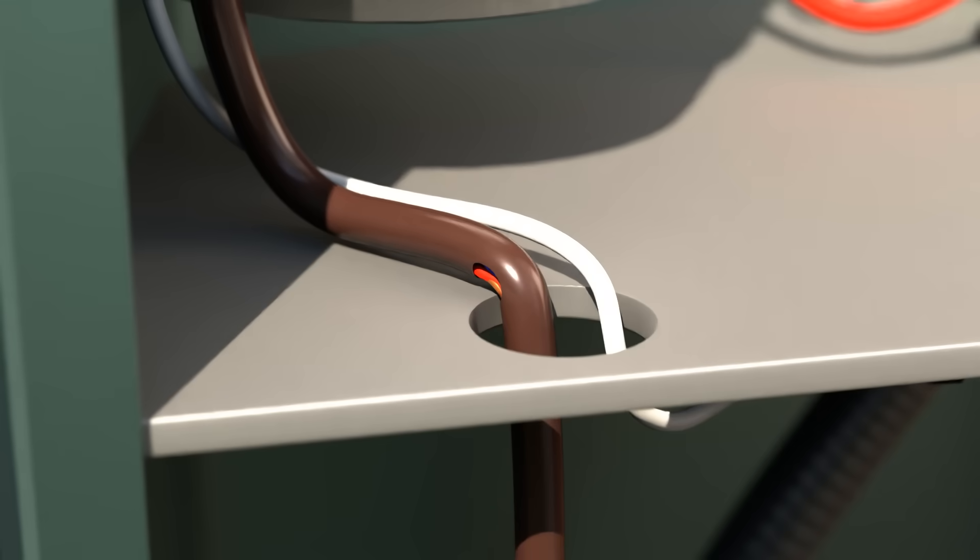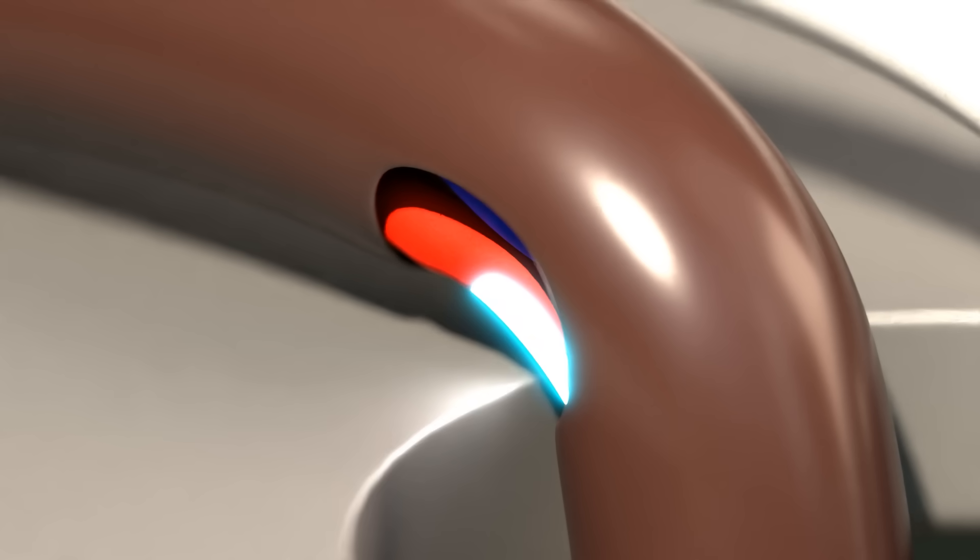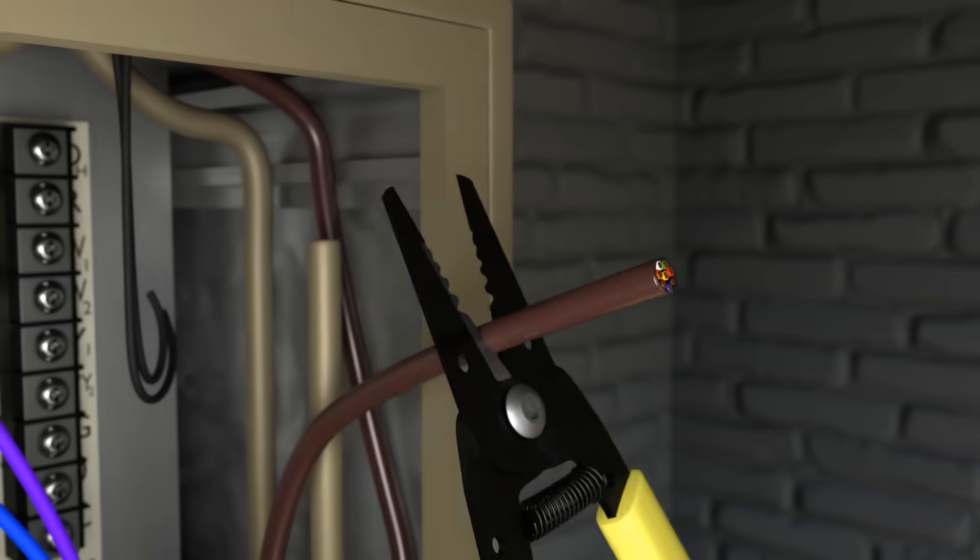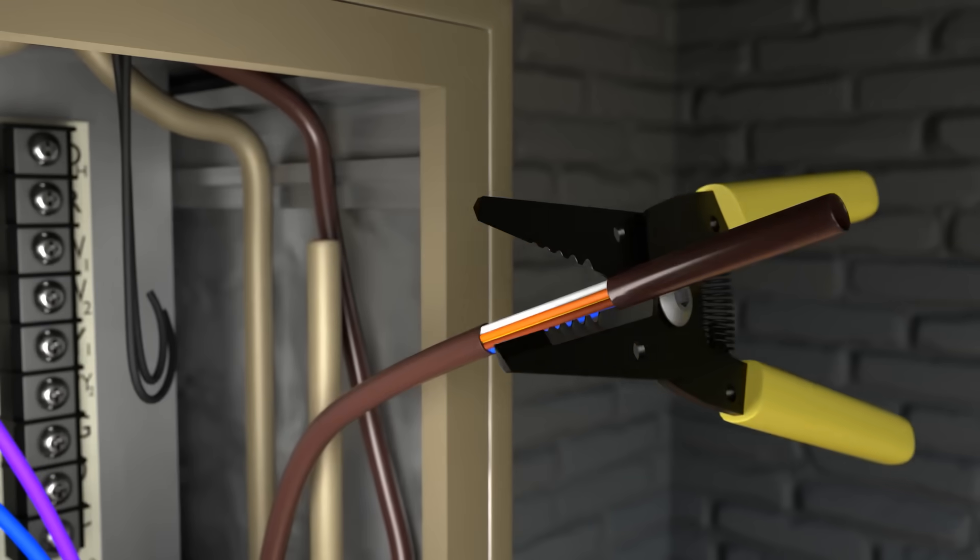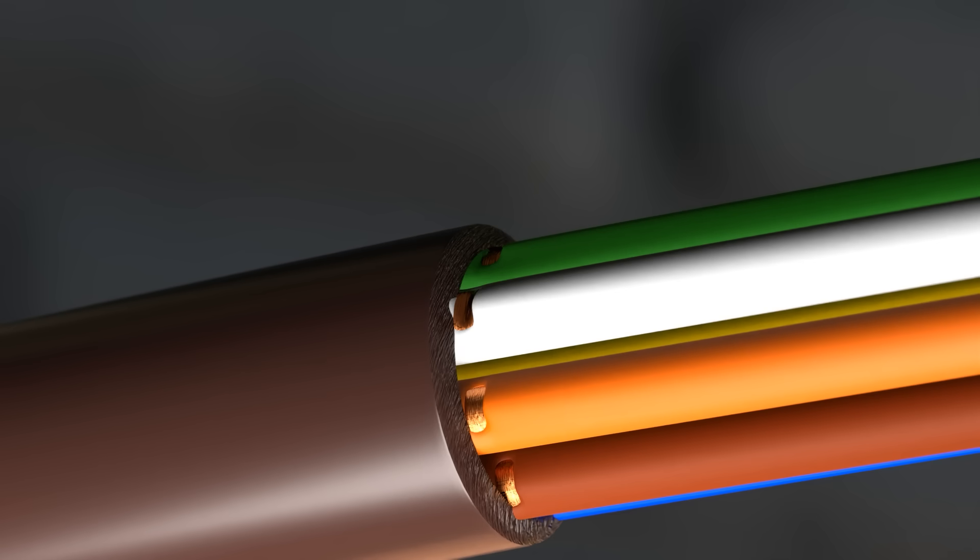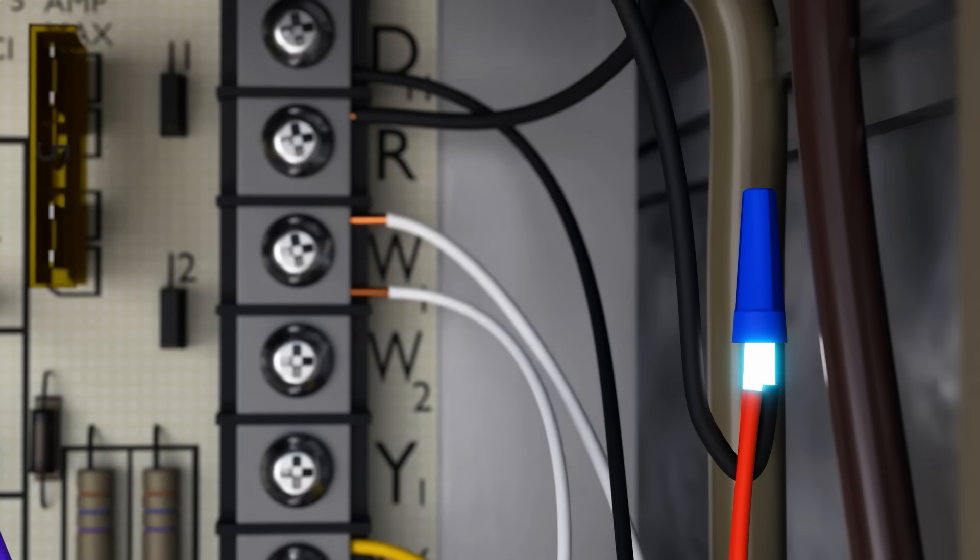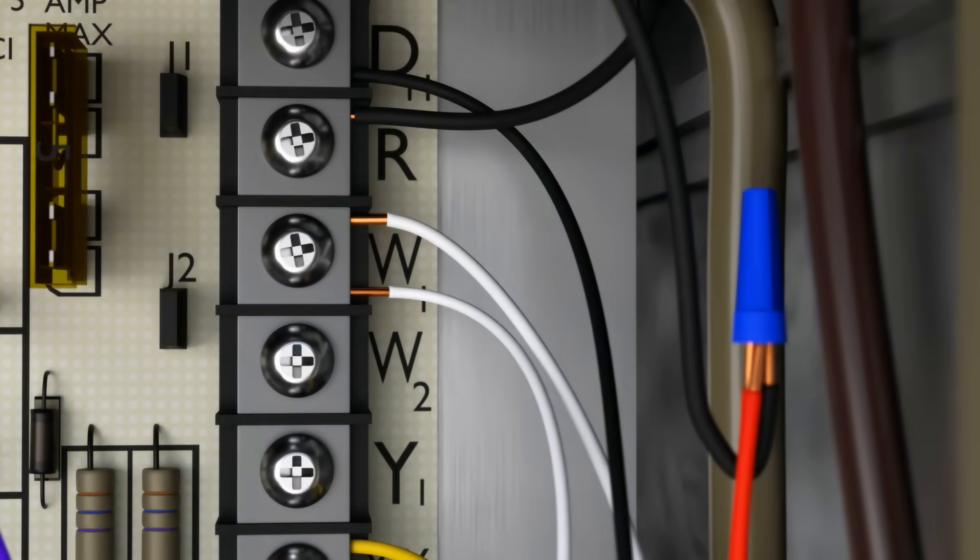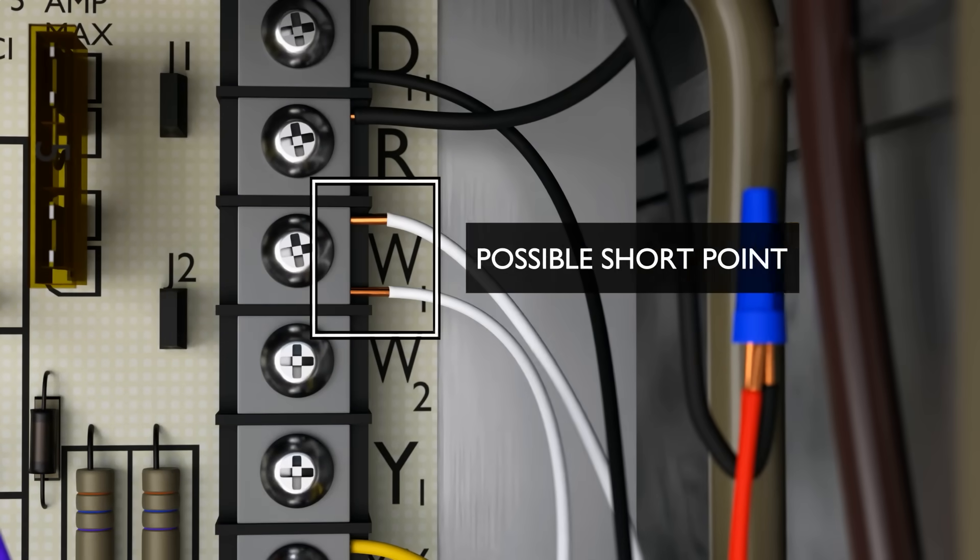Again, short circuits can happen in many places, often where conductors run through cabinets. In many cases, it happens because technicians strip back the wire jacket, as shown here, resulting in nicks and damage at the base of the wires. This can result in either an open or a short. If conductors are stripped back too far, this can also result in bare conductors that can result in a short where it touches other wires or ground.